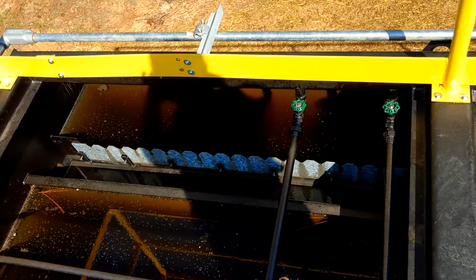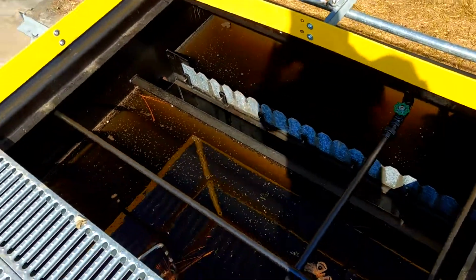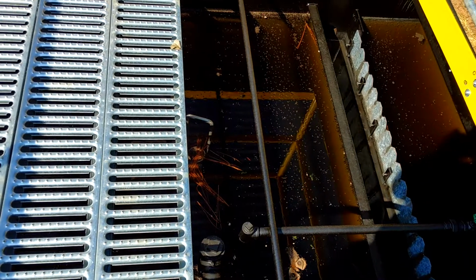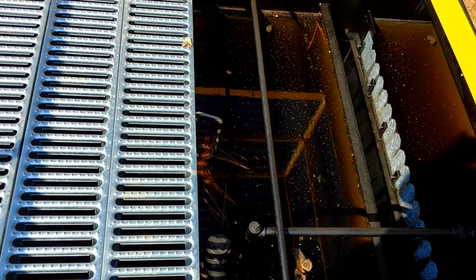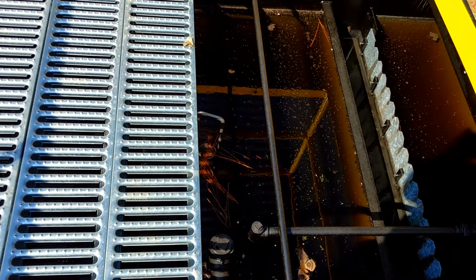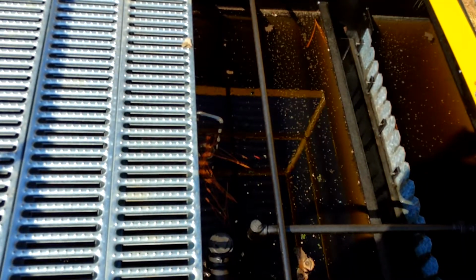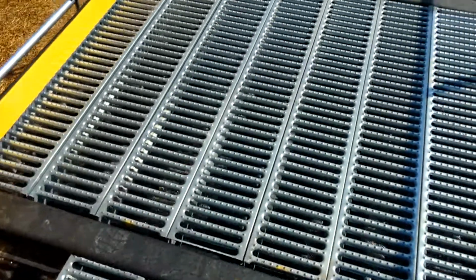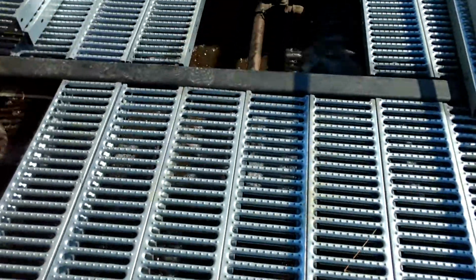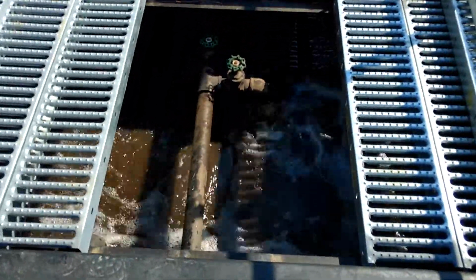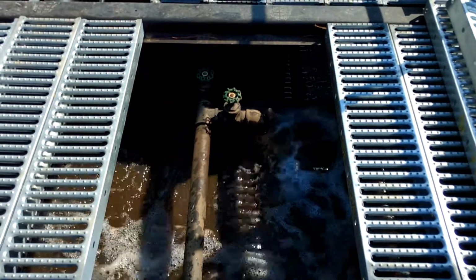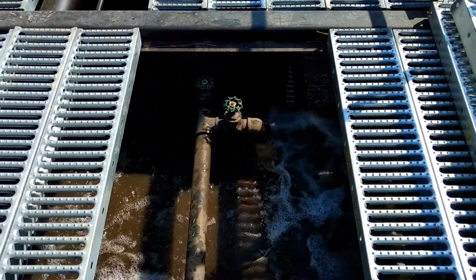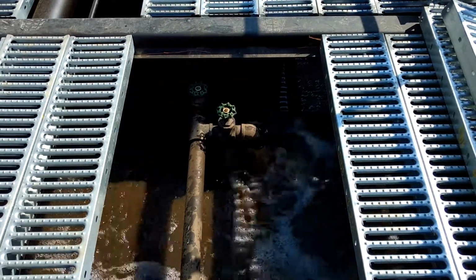and it's discharged. As activated sludge settles in the bottom of the clarifier, it is being continually returned so that we are not filling the clarifier up with activated sludge, but rather pumping it out and returning it back to the aeration chamber where it can do some good. The bacteria in the clarifier do no good because they're not coming in contact with the raw wastewater. It all happens here.